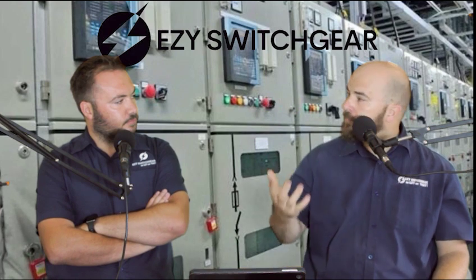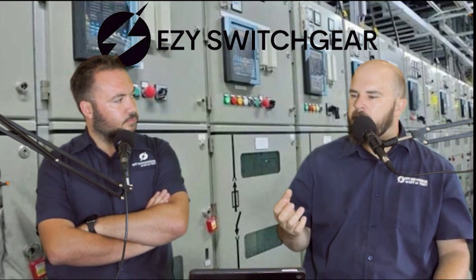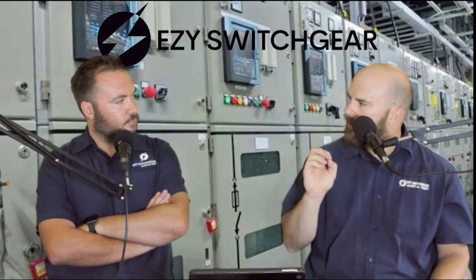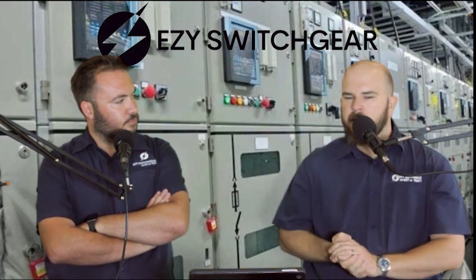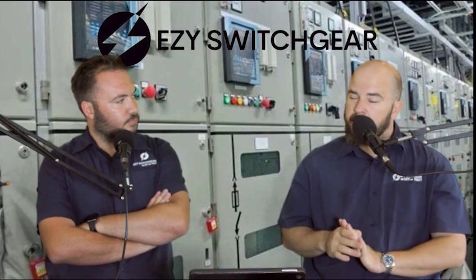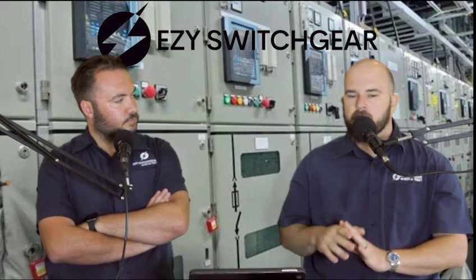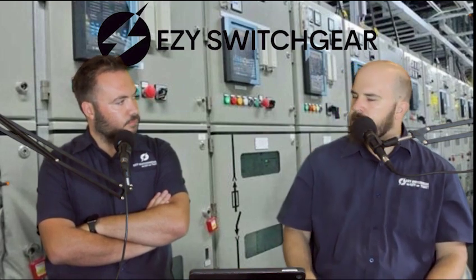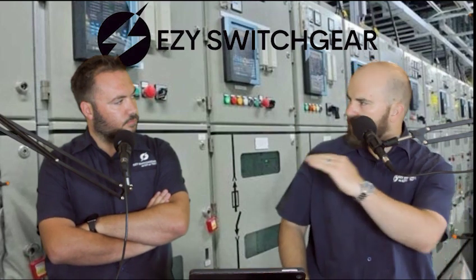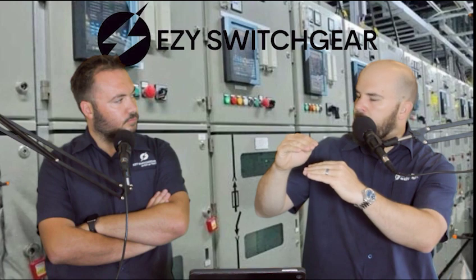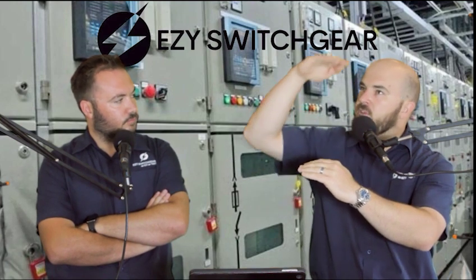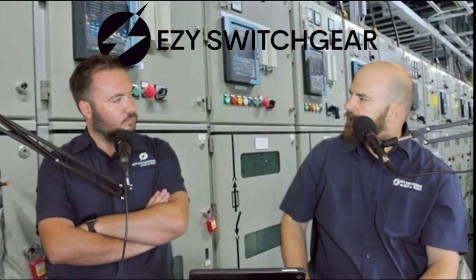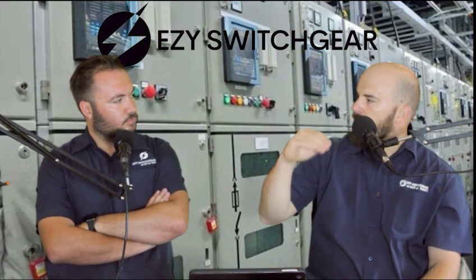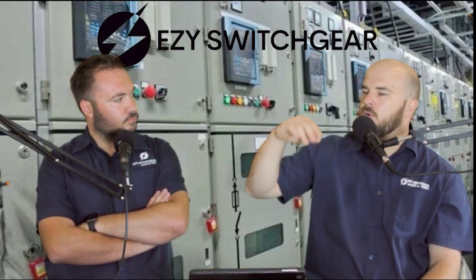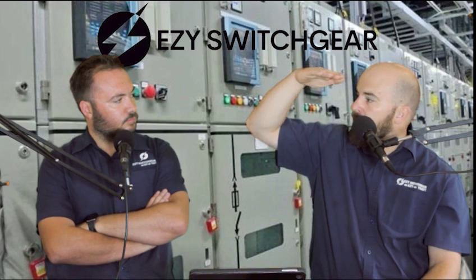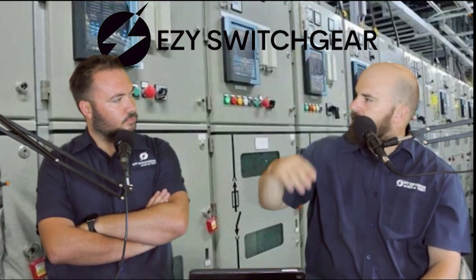The other thing is that moisture plays a big role in air insulated switchgear, and then design. Any sharp points can create that corona effect, which will make it easier to jump. So air insulated switchgear is designed incredibly well to get to the levels of insulation needed. In switchgear insulation we talk about the nominal voltage, the design voltage, your electrical insulation voltage, and then your basic impulse level. For instance, you would get an 11 kV switchgear with a power frequency insulation of 28 kV, and then also the BIL, the basic impulse level, which is then at 95 kV or 125 kV.